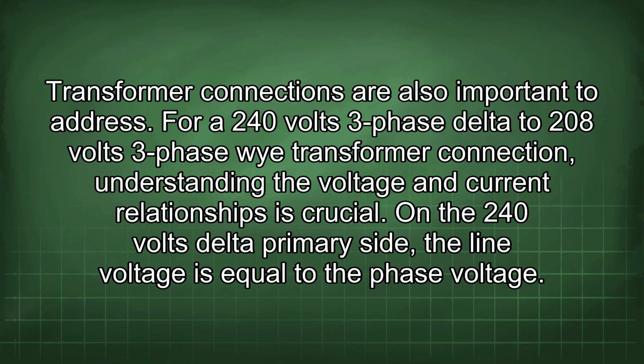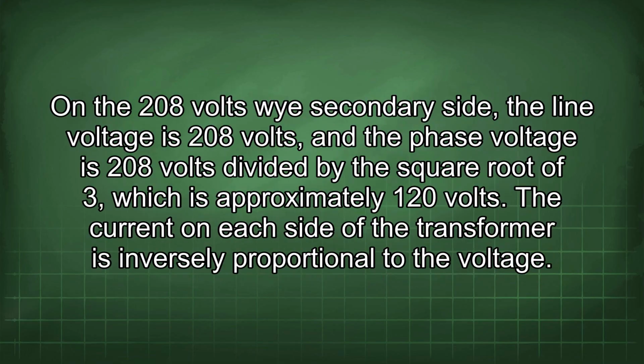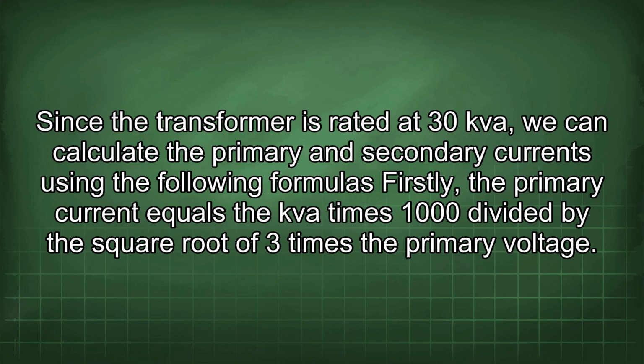For a 240 volts 3-phase delta to 208 volts 3-phase Y transformer connection, understanding the voltage and current relationships is crucial. On the 240 volts delta primary side, the line voltage is equal to the phase voltage. On the 208 volts Y secondary side, the line voltage is 208 volts, and the phase voltage is 208 volts divided by the square root of 3, which is approximately 120 volts. The current on each side of the transformer is inversely proportional to the voltage. Since the transformer is rated at 30 kVA, we can calculate the primary and secondary currents using the following formulas.